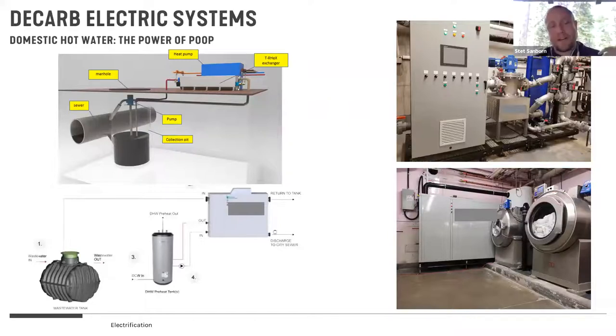So taking that wastewater stream, there's a storage container where your sewer water comes in, it goes into this tank and it flows by gravity out. We're able to pump that water out, which on a multifamily project is a beautiful 70 degrees Fahrenheit wastewater stream. It's an amazing source if you're trying to pull heat out of it. We run that through a macerator, a heat exchanger, and a heat pump to produce domestic hot water.